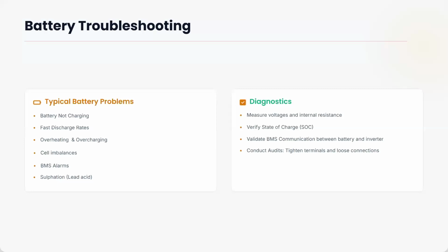But if they rise in temperature abnormally, you have done the installation and they are working, and this is happening, then it could be that the charger is bad. Maybe it's trying to force charge the battery, giving it more than the expected charge current, or overloading from the output. Because if a battery is overloaded, you are taking current that is higher than normal, then it will rise in temperature too. Or the terminals are not well connected. A good conductor of electricity is a good conductor of heat as well. If the terminal begins to rise in temperature because of poor or partial contact at the terminal, then it goes into the battery. The battery will rise in temperature. So you need to watch out for that.